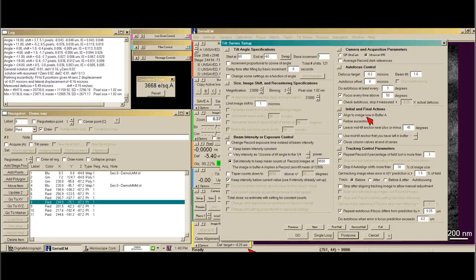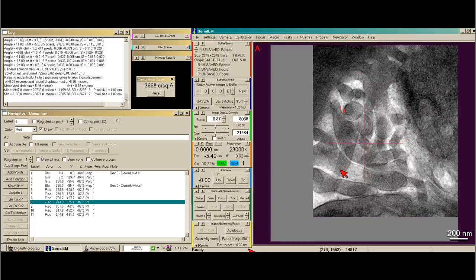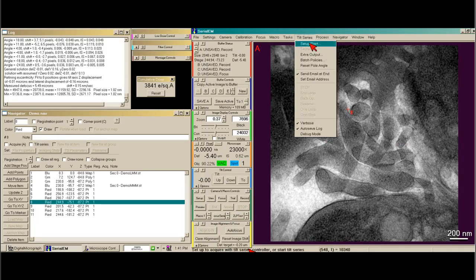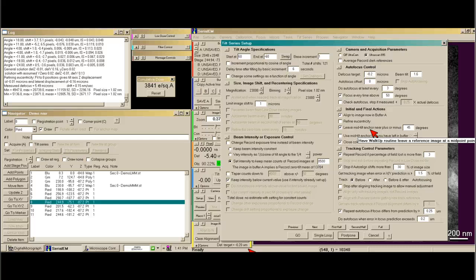I want to align to my image, which is now in buffer A. Let's double-check that we like that image — that's a very good image. If it wasn't where I wanted to be, I could postpone, right-click and drag to center my area of interest, and take a new record. So now, for sure, the image is what I want and that is in buffer A. I'm not going to refine eucentricity because we just did it. If you're worried about your sample being centered after it walks up to high tilt, you can leave a mid-tilt anchor at a certain degrees, usually around 40 to 45 degrees, and that will re-center everything in case something happened.